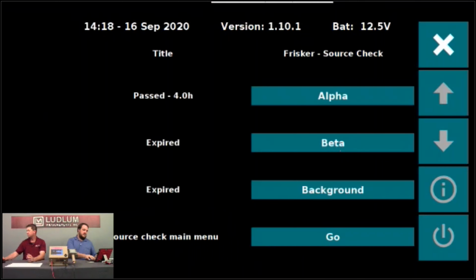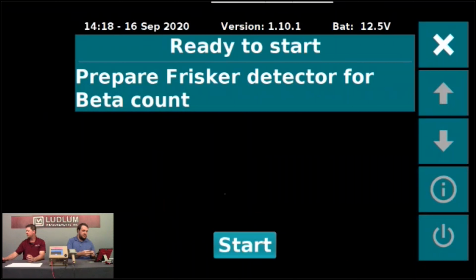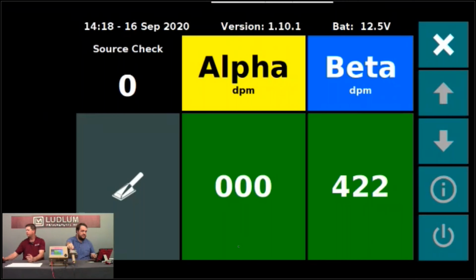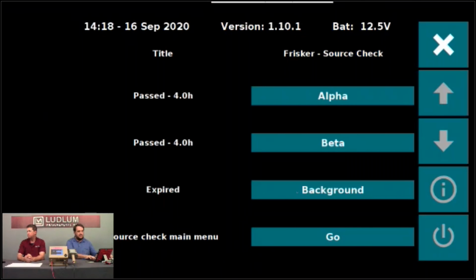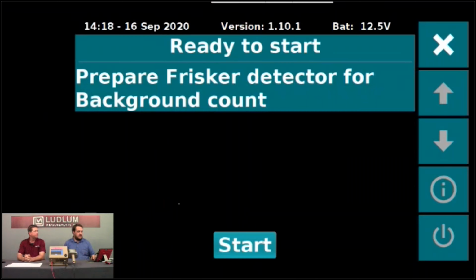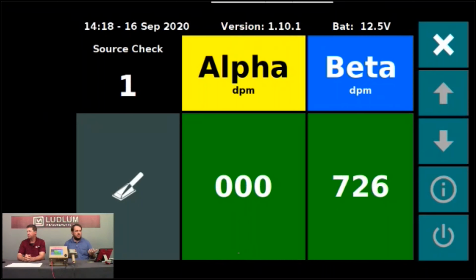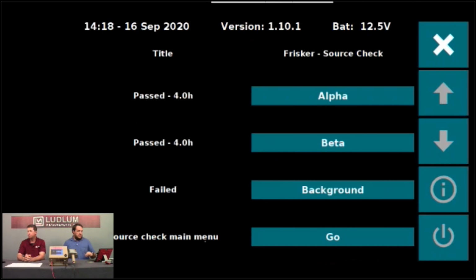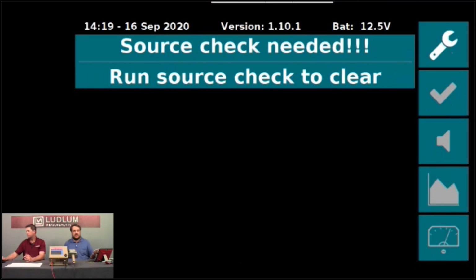We'll do the same thing for beta. Again, it asks you to prepare the detector, so then that's when you would put the source on it. Click start. It'll automatically start the count, and then again give you the results. And then the last one you'll have to do is the background. So if we start that one. This time I'm going to hit fail just to demonstrate what happens when a source check is failed. So over here on the left you can see the top two are passed, but the background in this case is failed. And if we go back to the main readings, the source check will still be expired basically, so it will be invalid. So the unit is not usable.